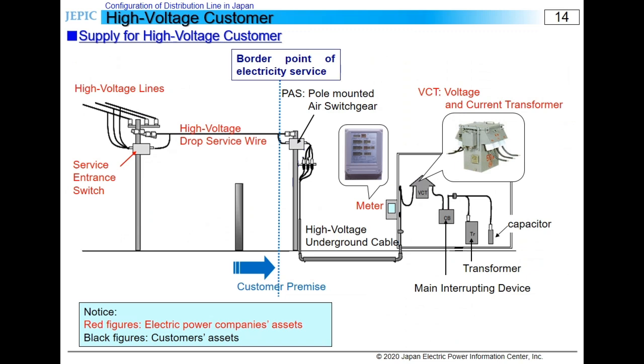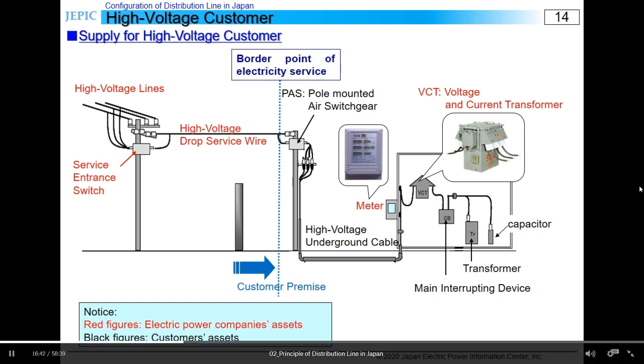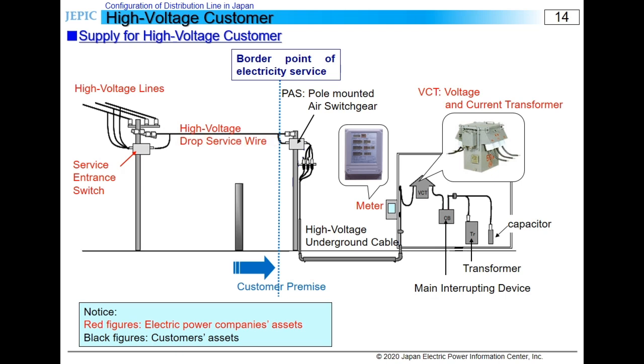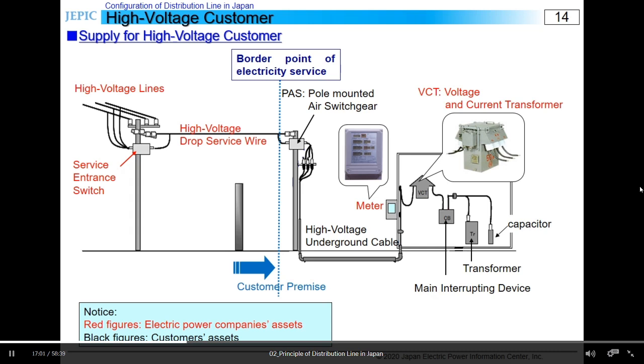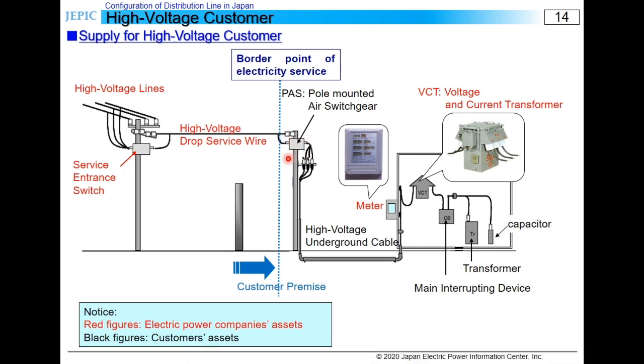Next, I'd like to talk about the equipment connected to high voltage customers. The same wires as high voltage line are used as high voltage drop service lines. The supporting structure which receives the drop service line belongs to each customer, which can be a pole or a wall of a building, and in any case, it has to meet technical standards. A switch called PAS is installed at the border point of electricity service, and when a failure of the customer facility occurs, it can cut it from the power grid.